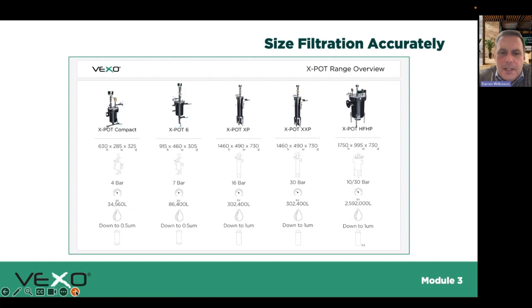So if you are looking to select any kind of equipment, but let's focus on filtration, it's really important to work with the OEM or the manufacturer of the equipment you're looking to install, but also just make sure you double check, do your own homework, that you're selecting the right equipment. And I don't mean that in any sort of demeaning way. But selecting the right equipment at the right size, at the right operating temperatures to meet the demands of that system. I've come across problematic jobs where pressure vessels weren't sized correctly. There's been pressure step degassing on heating, and the temperature of the system is way hotter than the manufacturer recommends for their equipment. So you start having all these issues, and it can take months before you get to the root cause.